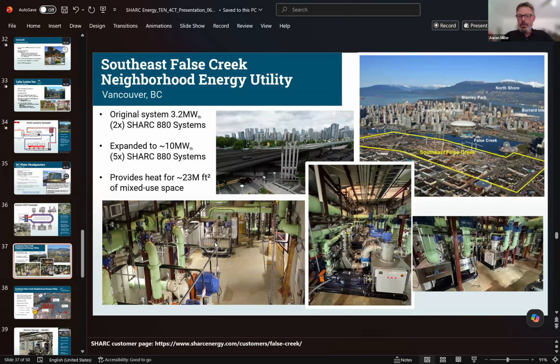This is a wastewater collection center that's literally parked under this overpass in the center of the city. It just happens to be where several large gravity sewer mains and a forced main all collect before they then get pushed down to the wastewater treatment plant. So this was a natural collection point. We put two of these SHARCs in there, and we were providing 3.2 megawatts to provide the hot water for this center core of Vancouver, right?